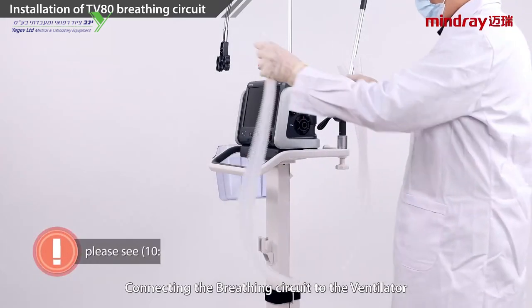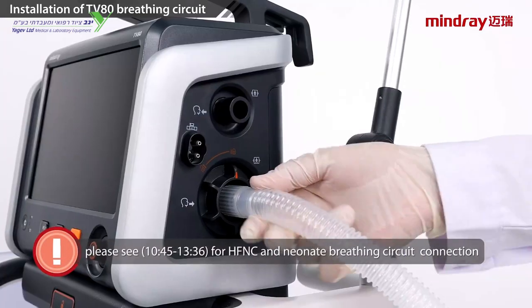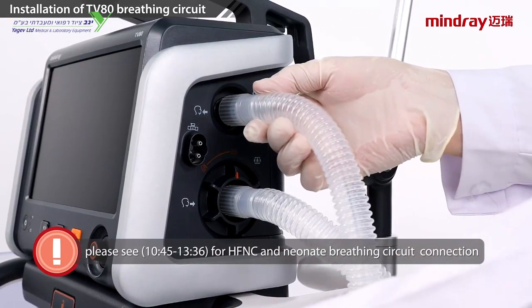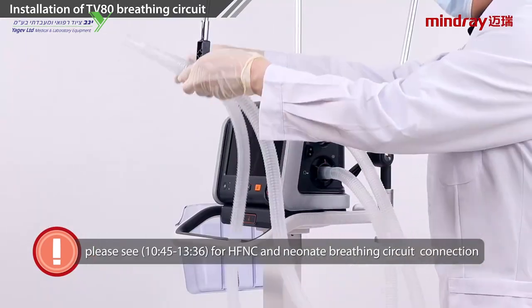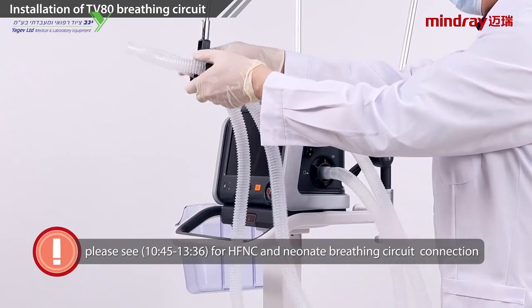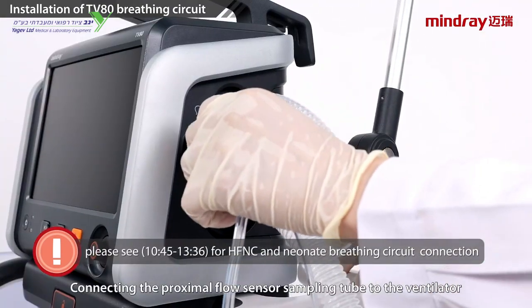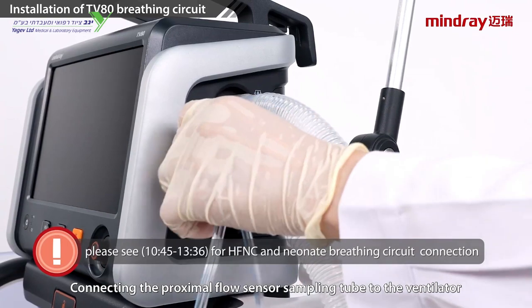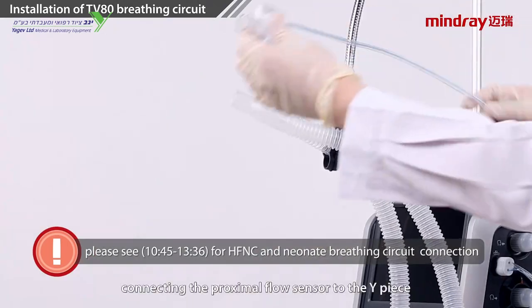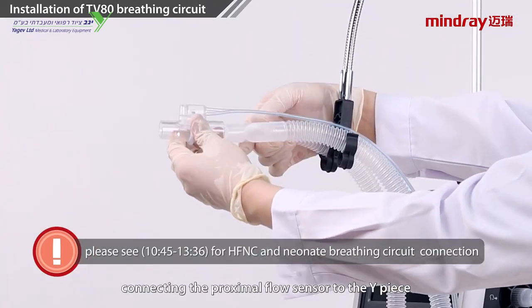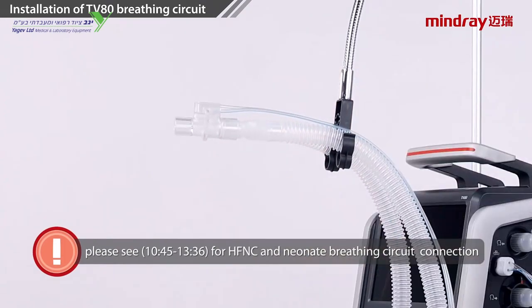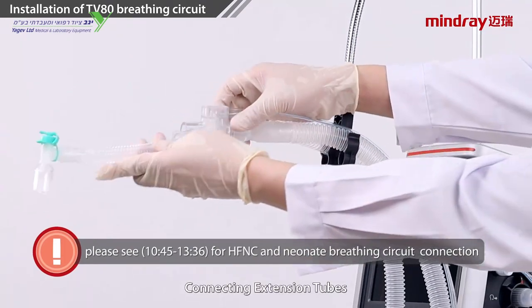Connecting the breathing circuit to the ventilator. Connecting the proximal flow sensor sampling tube to the ventilator. Connecting the proximal flow sensor to the Y-piece. Connecting extension tubes.